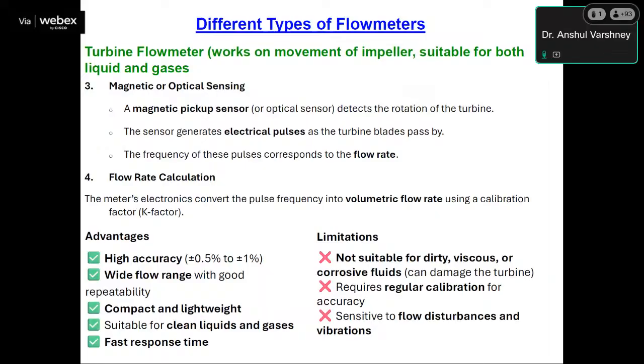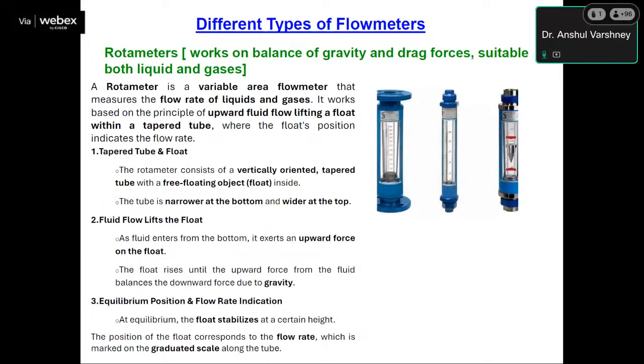The advantage of the turbine flow meter is that the accuracy is pretty good, between 0.5% and 1%, and it can be used for a wide flow range with good repeatability. They are compact and lightweight, suitable for clean liquids and gas, and the response time is quite good. However, this type is not suitable for dirty, viscous, or corrosive fluids. It can damage the turbine, it requires regular calibration for accuracy, and it is sensitive to flow disturbance and vibrations. Next is the rotameter.